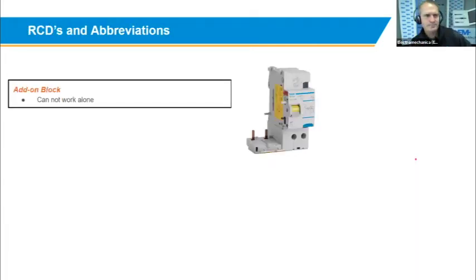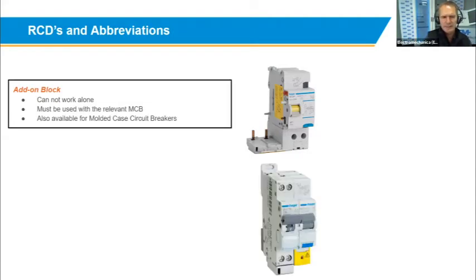Here we go. An add-on device by itself cannot work. It cannot open or close a circuit. By itself, it can do nothing. But combined with the relevant circuit breaker, it actually becomes an RCBO, a residual current circuit breaker with overload. The advantage of something like this is that in this application, the BDC240 is a 40 amp unit that can handle up to 40 amps.